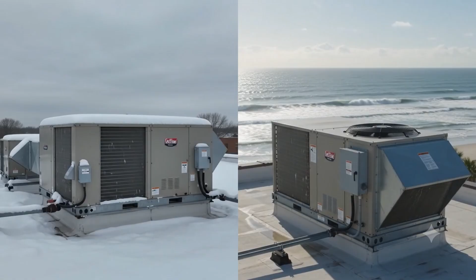We are changing subjects now to geography and environmental PM adjustments. Geographic and environmental factors must be taken into consideration for customizing your preventive maintenance tasks. This ensures resident comfort and equipment longevity. Northern states: PMs must heavily prioritize pre-winter boiler teardowns, roof drain clearings before freeze-thaw cycles, and heat trace cable checks. Coastal states: PMs must include monthly coil washing on outdoor condensers to prevent salt air corrosion, plus hurricane shutter operational tests. When you write your master schedule, start with national standard codes like NFPA and OSHA. Be sure to include your state's specific administrative codes directly into the PM procedure description.